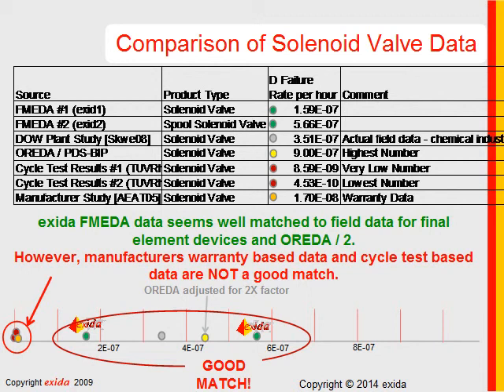We can compare mechanical parts as well as electronic. For solenoid valves, FMEDA has results for a poppet type and a spool type — FMEDA can distinguish between these two fundamentally different designs. Taking the average of those two numbers: 1.59e-7 plus 5.66e-7 divided by 2 is approximately 3.5e-7 — very close to the Dow study result. We confirmed with Dow engineers that their data includes all types of solenoid valves — poppet, spool, all designs — so taking an average brings the results very close.